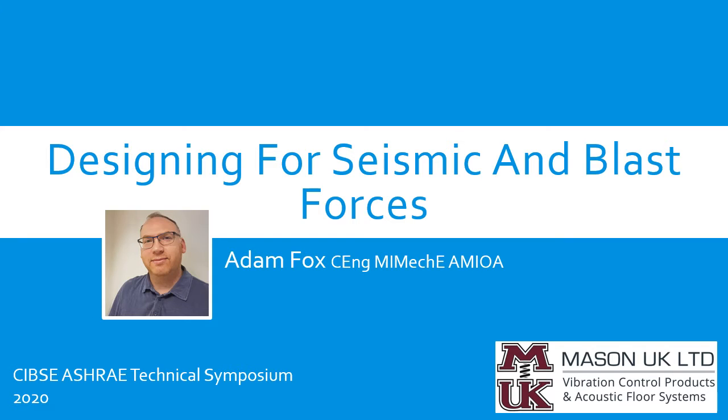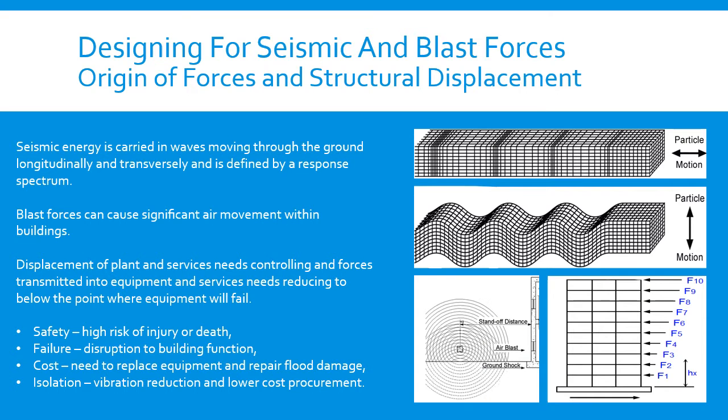Mason Industries is a long-time contributor to ASHRAE, and primarily we're responsible for controlling surface vibration and thermal movement, but our projects often have a seismic and blast criteria. Seismic and blast are intrinsically related. Surfaces placed in these environments have to accept the forces which result from rapid displacement in all directions. Primarily, the difference between the two is duration.